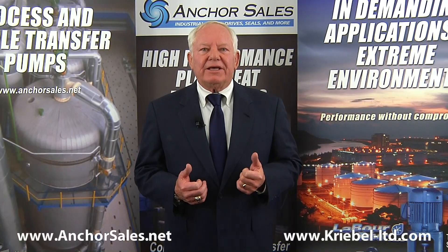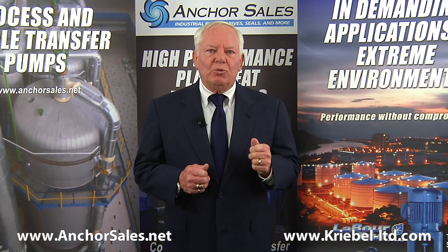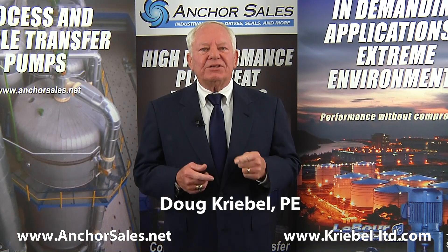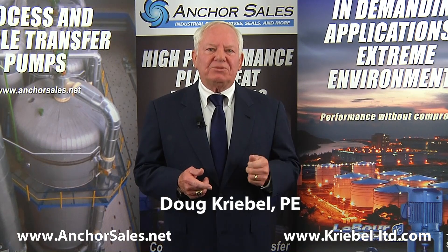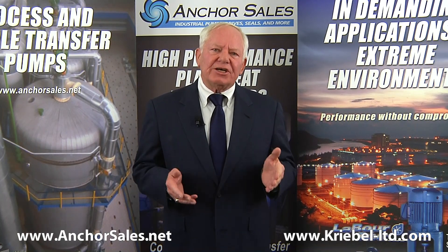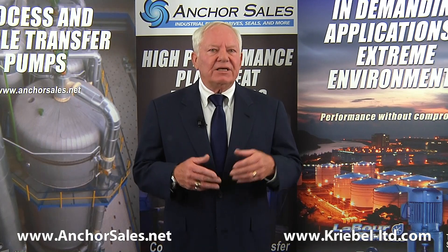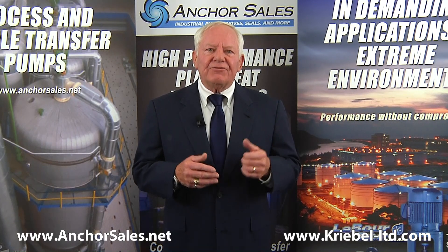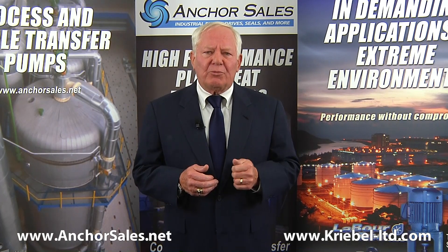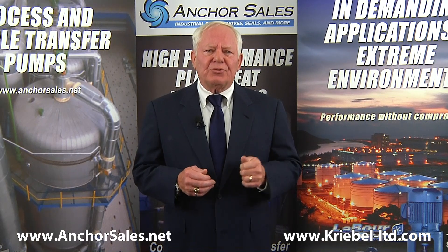A unique but common application of centrifugal pumps is boiler feed water — feeding water into a boiler. I'm Doug Creeble and I'm here to discuss boiler feed water pumps in general. Boilers can range from 100 PSIG for general steam heating, to over 500 PSIG for process steam, 1700 PSIG for combined cycle power plants, 2400 PSIG for coal-fired power plants, and over 3000 PSIG for supercritical boilers.